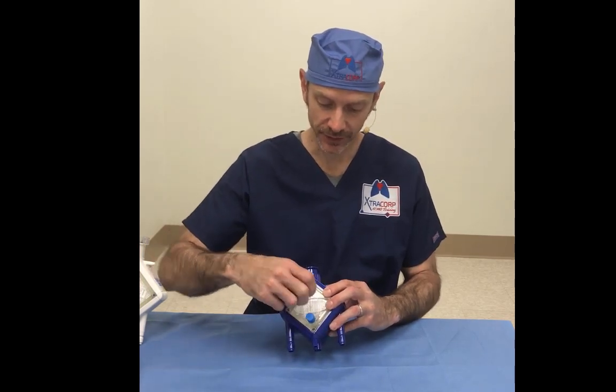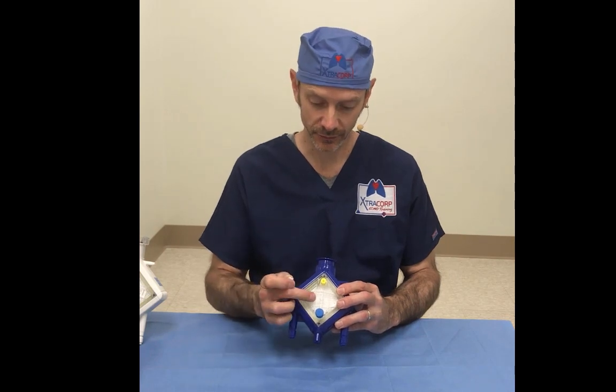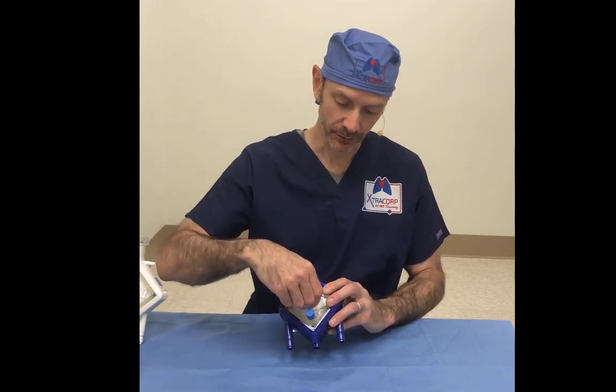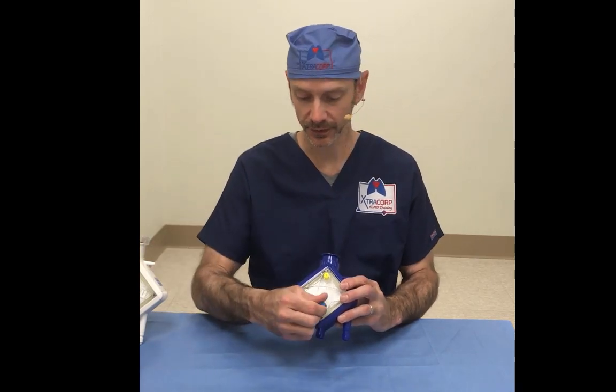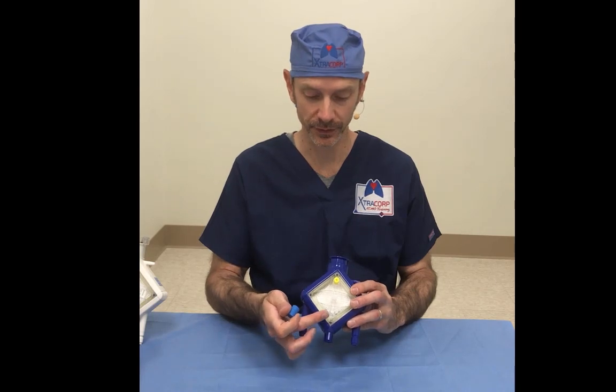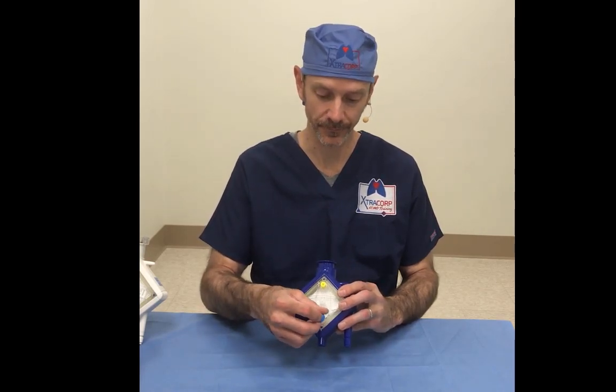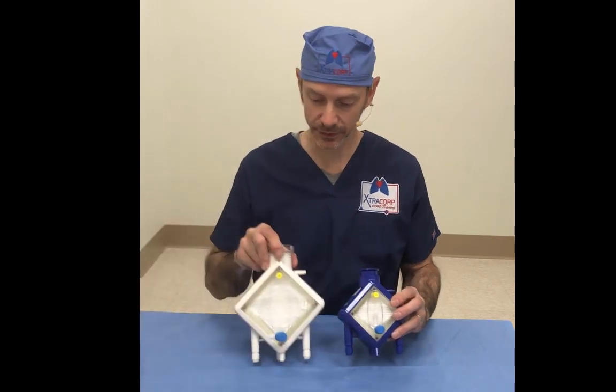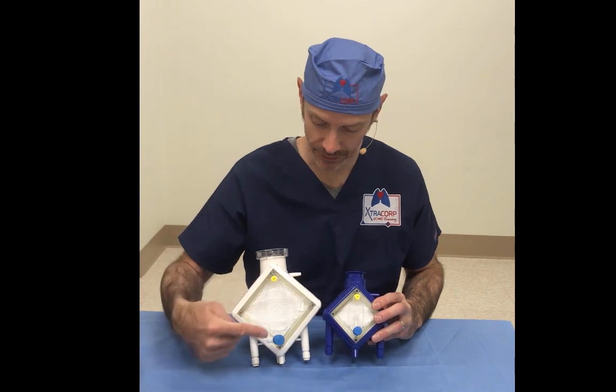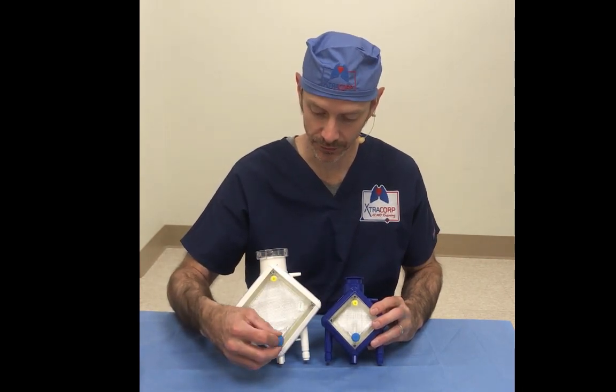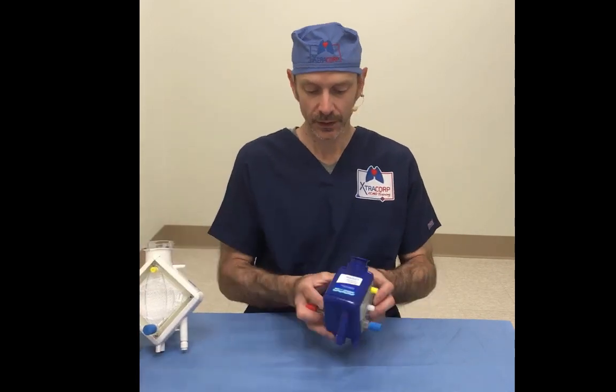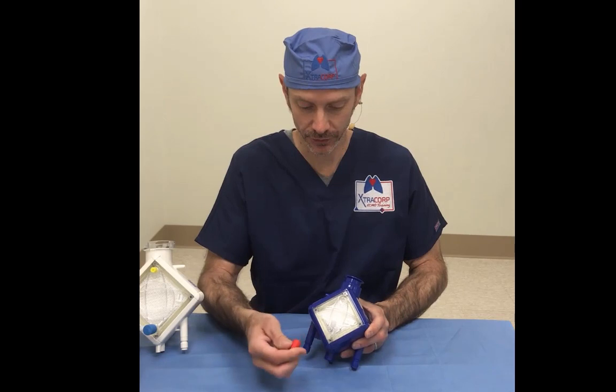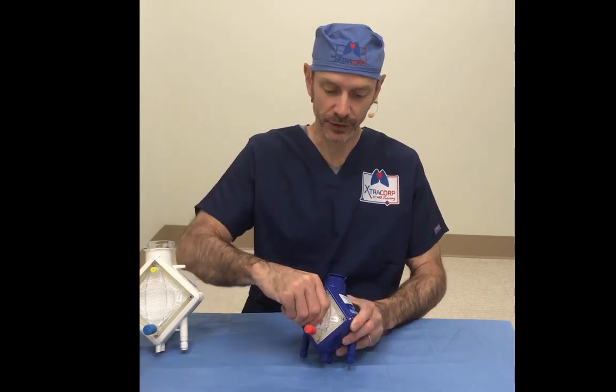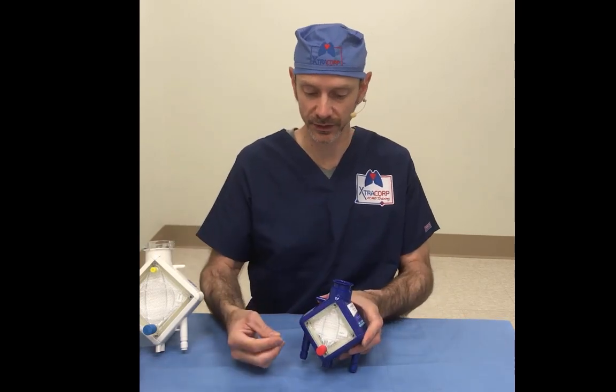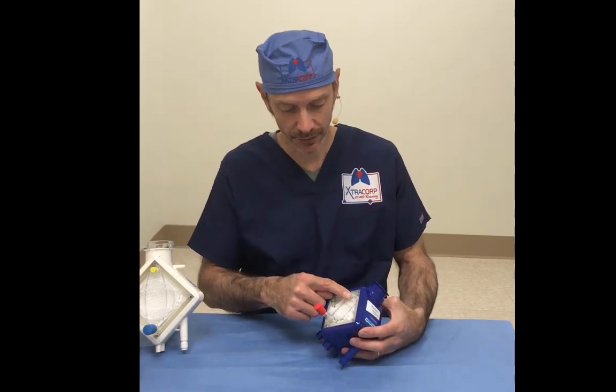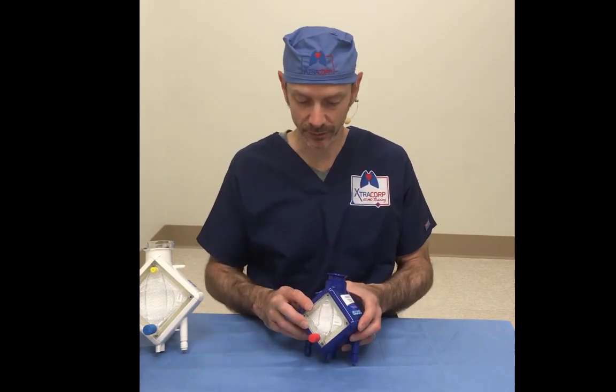On this pediatric unit, there is a luer connection here that does communicate with the blood phase, and that could be used for your pre-membrane pressure monitoring, because there's no connection for pre-membrane monitoring on the 1/4 inch connection that's down here. And that's different than the adults. In the adults, that pressure port is on the inlet where you put your tubing. On the outlet side, we have the 1/4 inch connection that goes to your tubing, arterial line back to your patient. We have a pressure monitoring luer connection that does communicate with the blood phase, and we have another pressure port up here that does communicate with the blood phase.